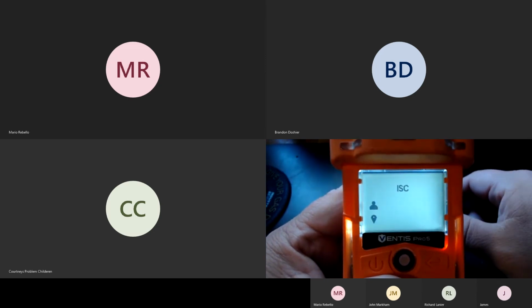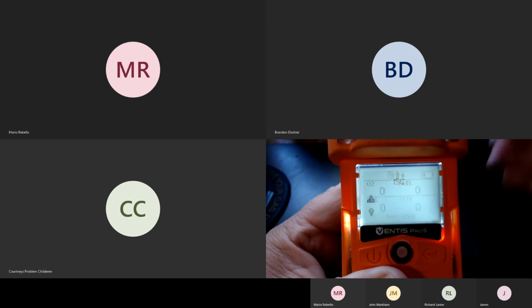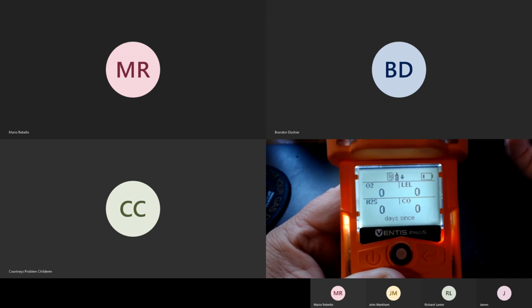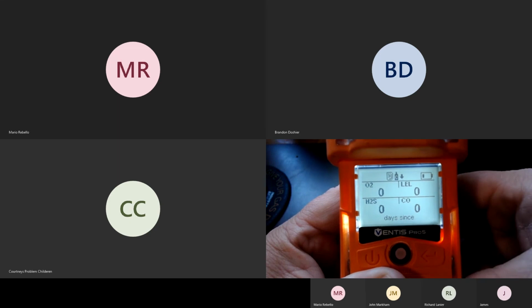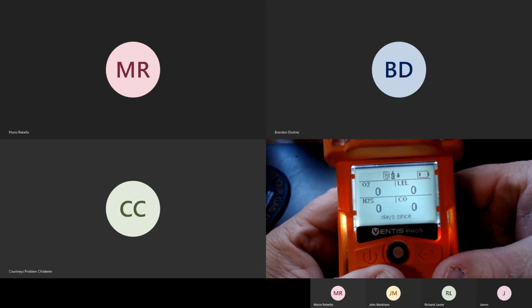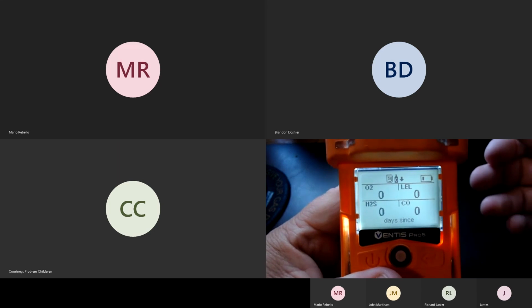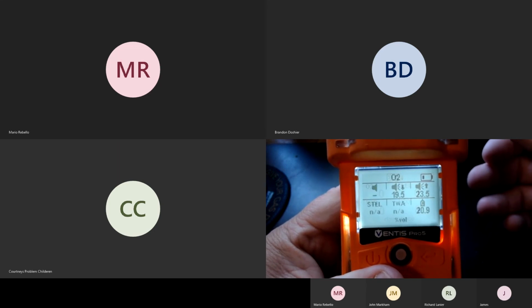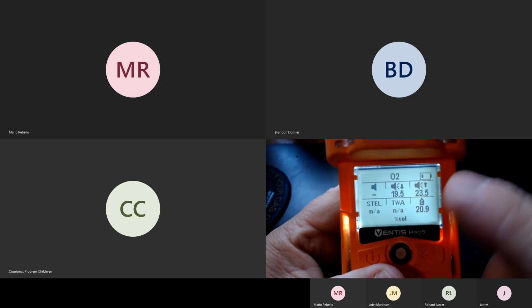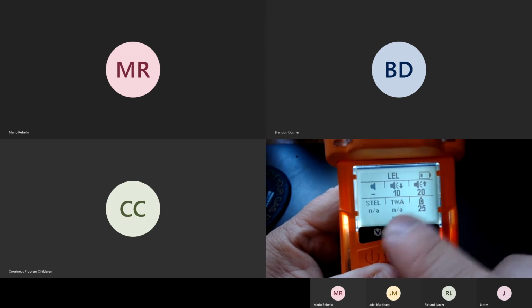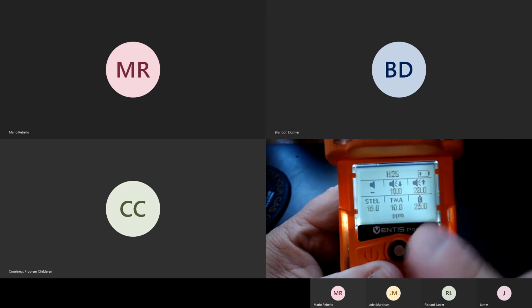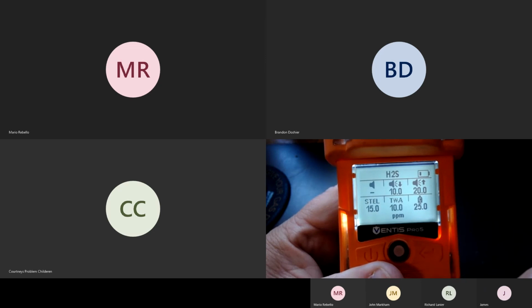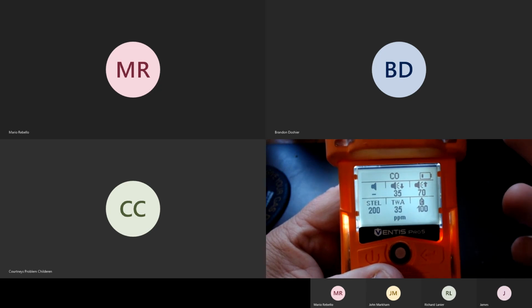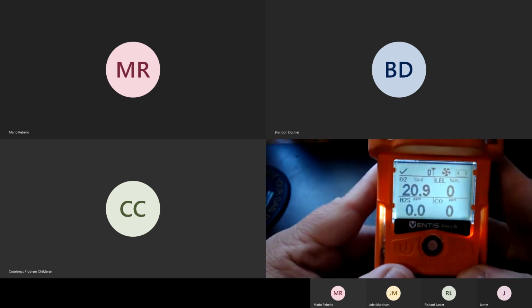These things do have wireless capabilities built into them for communication from instrument to instrument and device to device. So if you ever do upgrade to any of that kind of stuff, it has all those wireless features in there. It takes a couple more seconds, and then it shows us each sensor and all the settings for each sensor. Right here is my O2 sensor with its low alarm and high alarm, then LEL, low alarm, high alarm. Then it will do H2S, low alarm, high alarm, STEL, TWA, and then the same thing for CO. Yours will give you one more since you do have HCN in your instrument. I don't have HCN installed in this one.